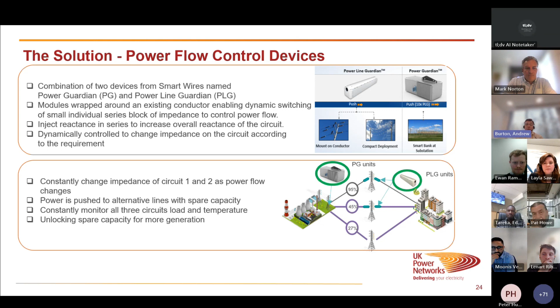We then started to look at the deployment of these and where they need to be deployed. We can deploy them across the two circuits, circuit 1 and circuit 2. As the impedance changes, we're able to constantly update and dynamically change it with the deployment of the power line guardians. We're able to monitor the circuits and the temperature, and push power onto the spare capacity across the other two lines. This can unlock more spare capacity for more generation to be connected.